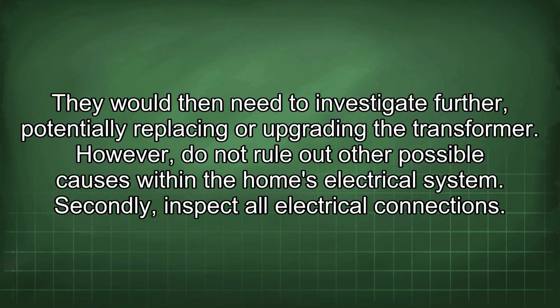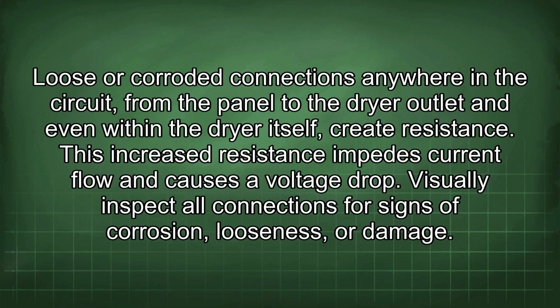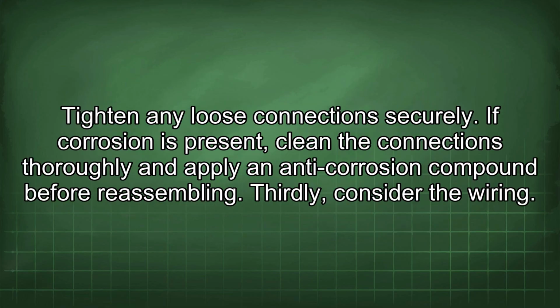However, do not rule out other possible causes within the home's electrical system. Secondly, inspect all electrical connections. Loose or corroded connections anywhere in the circuit from the panel to the dryer outlet, and even within the dryer itself, create resistance. This increased resistance impedes current flow and causes a voltage drop. Visually inspect all connections for signs of corrosion, looseness, or damage. Tighten any loose connections securely. If corrosion is present, clean the connections thoroughly and apply an anti-corrosion compound before reassembling.